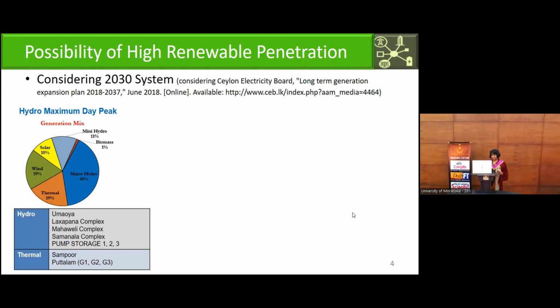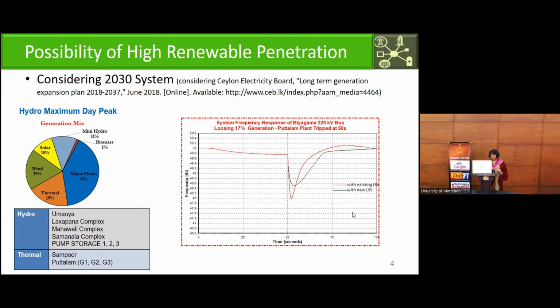In that situation, N-1 contingency is considered here, a tripping of one plant, under a situation where solar is ramping down. The system could come back and be stable. The red line shows the system with the existing load shedding scheme, that is, the existing system as proposed to 2030. And actually we did this study for proposing network upgrades, introducing a dynamic load shedding scheme.